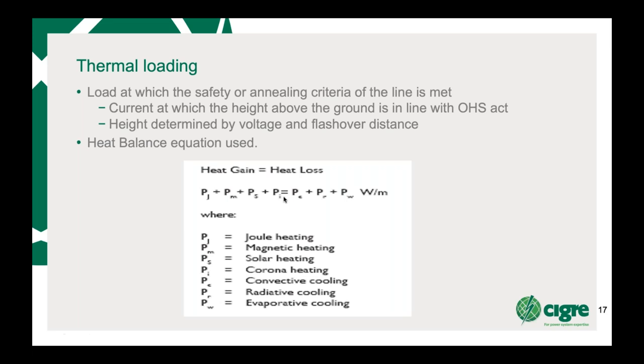On the cooling side, you've got convective, radiative, and evaporative cooling. Again, evaporative cooling is considered to be ignored because it's an incredibly high cooling effect when the conductor is wetted. But you have to be certain that the entire line has wet conductor, which is not always possible to do.